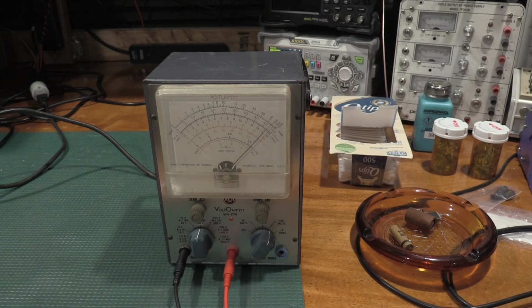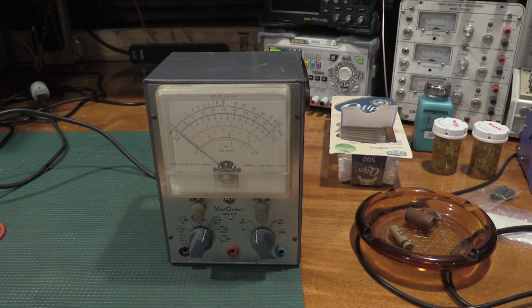So now it wants us to do, I'm going to do 120 volts on the 150 volt range, but we're going to use the AC frequency standard for that. So let me switch over the 7510, get the AC standard set up, and then do the last adjustment point. Okay, let's move our signal up here. We've got 115 volts on the test leads.